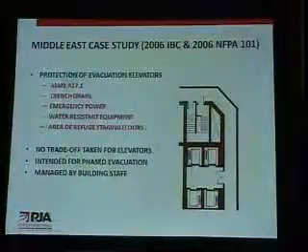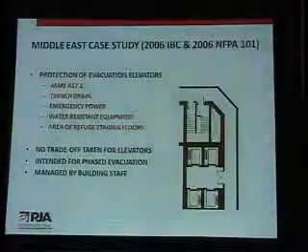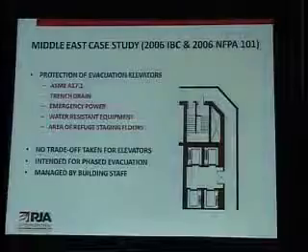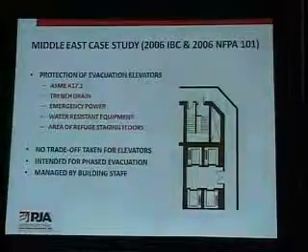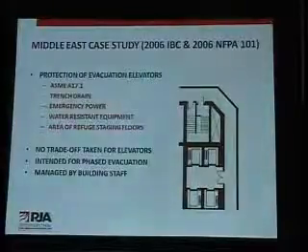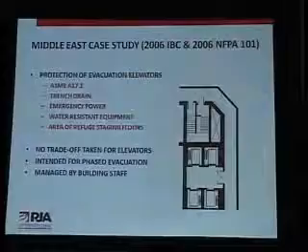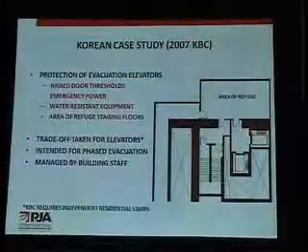Now, this corner of the floor is mirrored onto the other corner of the floor as well. In this building, however, similar to Burj Dubai, we did not take any trade-offs for elevators, so the stairs have been sized to accommodate the occupant load for the tower. But again, it's the phased evacuation managed by building staff.